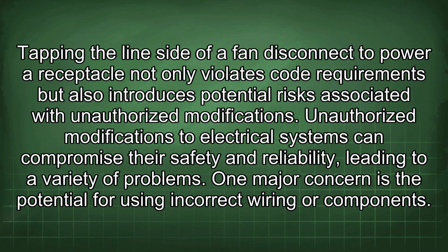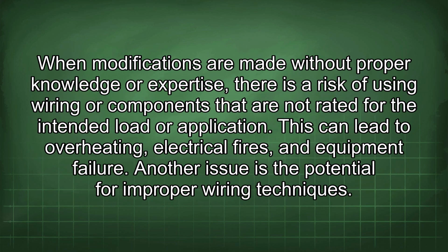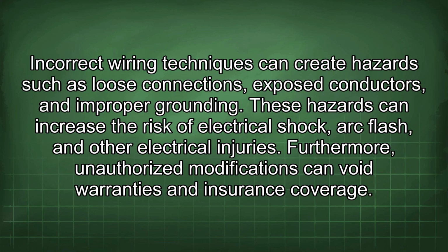Unauthorized modifications to electrical systems can compromise their safety and reliability, leading to a variety of problems. One major concern is the potential for using incorrect wiring or components. When modifications are made without proper knowledge or expertise, there is a risk of using wiring or components that are not rated for the intended load or application. This can lead to overheating, electrical fires, and equipment failure. Another issue is the potential for improper wiring techniques. Incorrect wiring techniques can create hazards such as loose connections, exposed conductors, and improper grounding. These hazards can increase the risk of electrical shock, arc flash, and other electrical injuries.